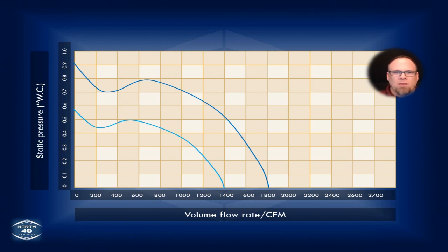We know most manufacturers want you to set up an air conditioning system to operate at 400 CFM per ton on most. Some of them are at 350 CFM per ton. But if you look at the 400 CFM per ton, what that's telling you is a 1-ton unit would use 400 CFMs, a 2-ton unit's 800, a 3-ton unit is 1200 CFM, and you're trying to set it up for that value. Okay, so how do you figure out where that actually lands?